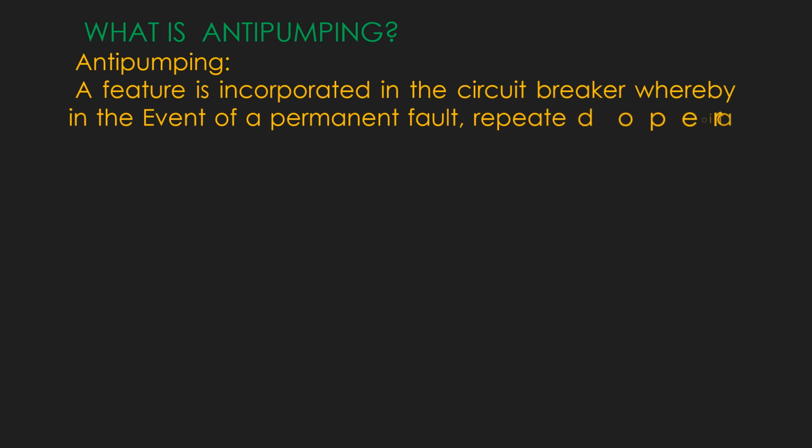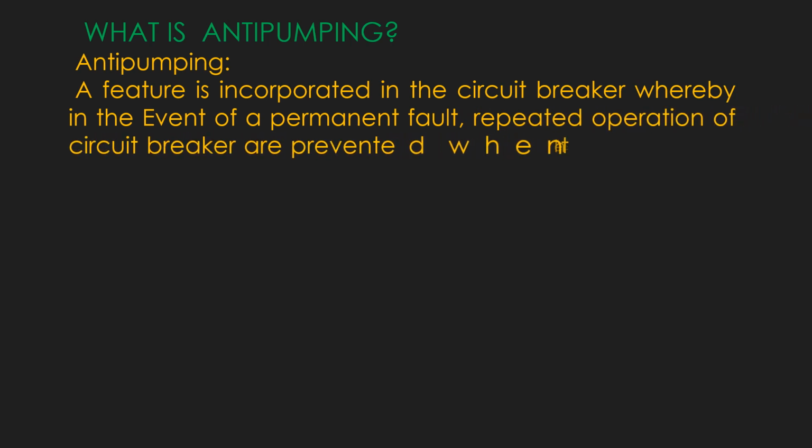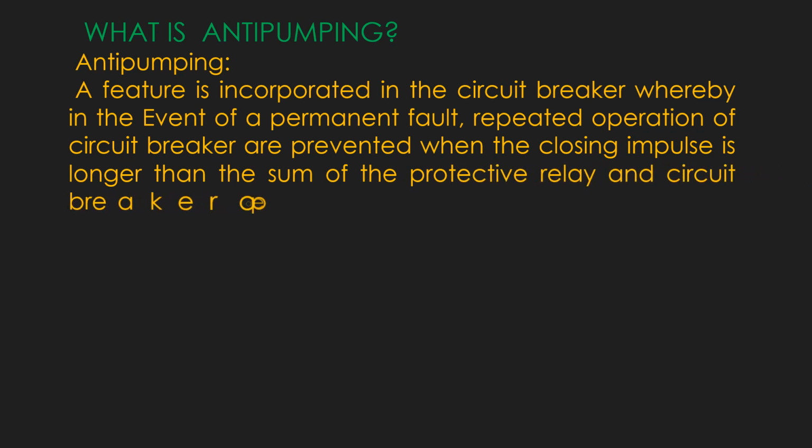What is anti-pumping? A feature is incorporated in the circuit breaker whereby, in the event of a permanent fault, repeated operation of the circuit breaker is prevented when the closing impulse is longer than the sum of the protective relay and the circuit breaker operating times.